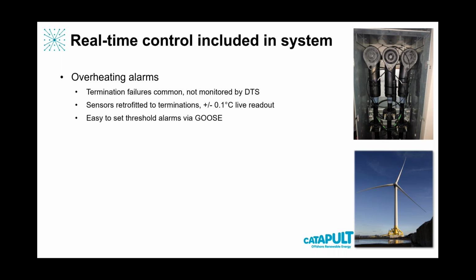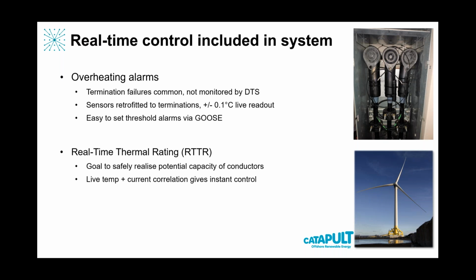They're very sensitive, and you can easily set a threshold alarm and send a GOOSE message to warn of a problem. And because you can combine temperature monitoring and current monitoring or voltage monitoring at the same time, it means you can get to the goal of safely realizing the potential capacity of these cables, because if you've got live temperature and current correlations, you've got instantaneous control of how much current and load that system can take at any given time in real time. And real-time thermal rating, or what some people call dynamic line rating, is clearly something that's going to be of value in the future.